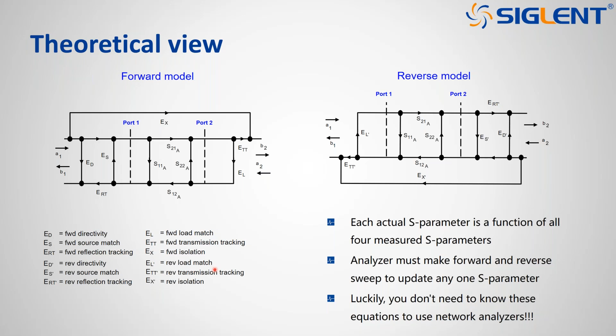What is a typical calibration procedure? I mentioned before we are using well-known standards to do measurements. So in this case, we're having a source, we're going down to an open. We exactly know an open returns full energy. So we know what we're sending into the system, but we receive something different. And with an open, we also have a phase shift. So we get the information how much phase shift is inherent in the system and how much attenuation or losses or frequency response over the frequency we have.